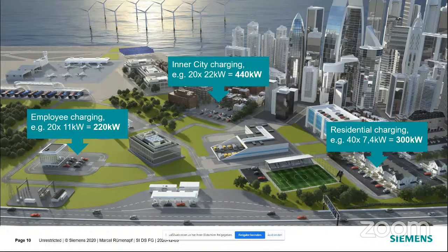In the center, it's also possible to have inner city parking, maybe at shopping malls or movie theaters. Here the time vehicles are connected could be a little shorter, so the power rating is chosen a little higher, for example 22 kilowatts, basically the maximum achievable with AC charging. If we want to electrify, say, 20 parking spots with 20 cars charging in parallel at full power, that would result in a total power demand of 440 kilowatts for this specific site.